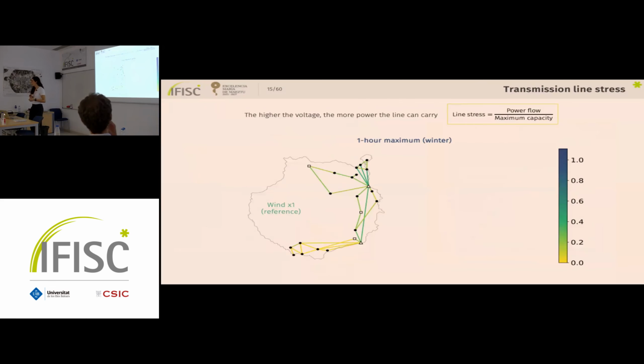We can also look at the stress of transmission lines, and the stress of a line basically tells us how close to its limits the line is. So it's the ratio between the power flowing through the line and its maximum capacity. And we can see here in the reference case that all lines are well below their limits, and the higher stress levels are observed here in the north, which is where the main consumption centers are located. In the case with more wind power, we observe that the stress now changes, especially in these lines, which are connected to the wind generation sites shown here with the square symbols and also with the arrows. And especially here, this short line in the south becomes overloaded.